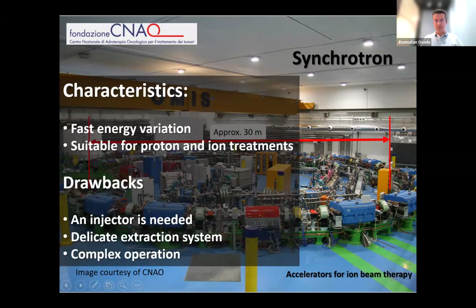And the good thing about these machines is that you can change the energy quite quickly. In the cyclotron, you cannot change the energy. You need to put in a mechanical energy degrader in order to control the depth, that is, the energy of the beam. The really nice thing about these machines is that they are suitable for proton and ion treatments. It's not only carbon, but also helium, so you can use whatever falls within the capability of the magnetic field that keeps the particle inside the trajectory. So you can use many ions in the synchrotron, which you cannot in the cyclotron. The drawback is a big machine.